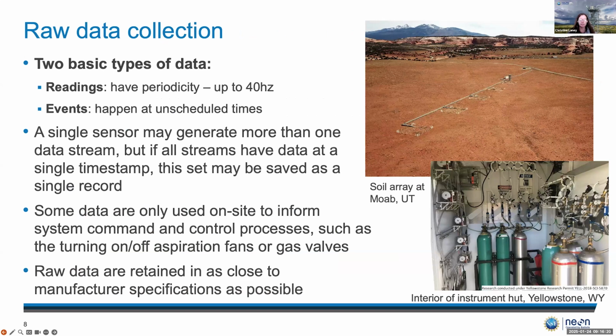When we talk about the raw data, we're essentially talking about two different basic types of data. One is the readings, which have periodicities up to 40 hertz, especially for our eddy covariance system. We also have events, which can happen at unscheduled times based on other data streaming in through the system. A single sensor can generate more than one data stream, but if all the streams contain data with a matching timestamp, then that set can be saved as a single record, which helps us save on storage and other things. Some of the data are only used at the site to inform system command and control processes to kick off events like turning on a fan or turning on a gas valve. The raw data are retained as close as possible to the manufacturer's specifications.